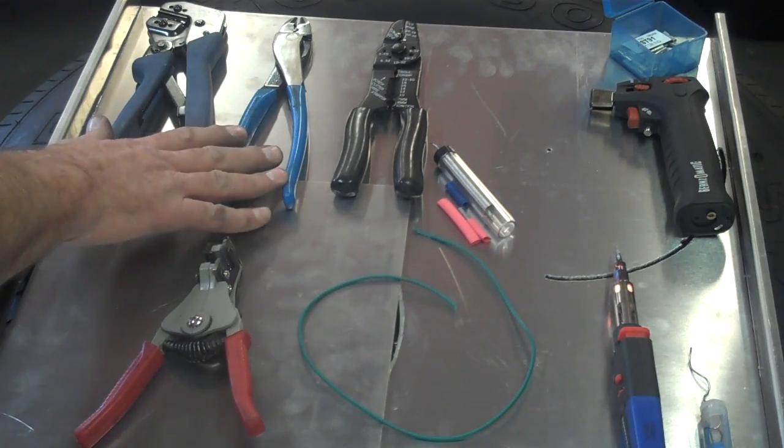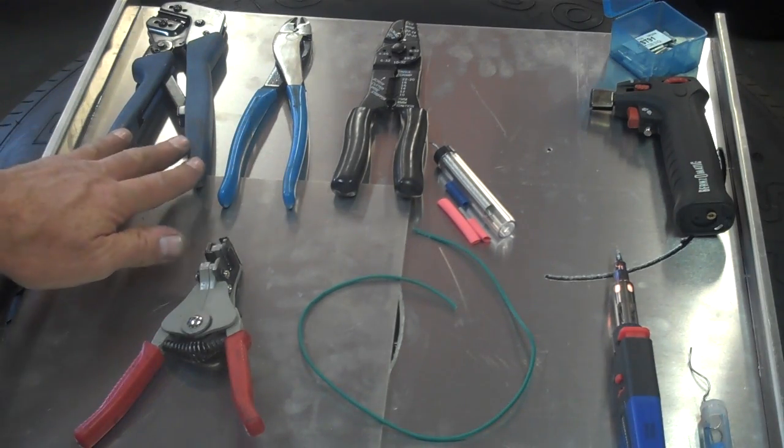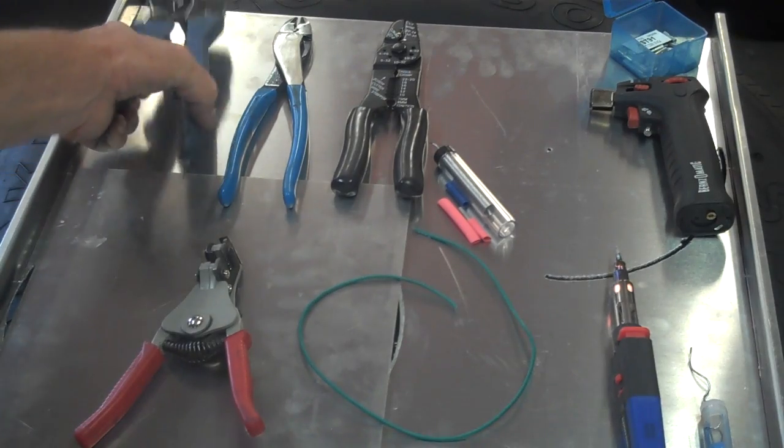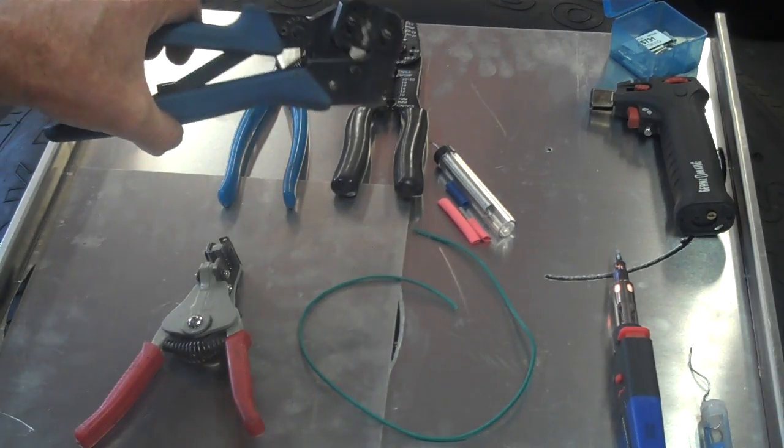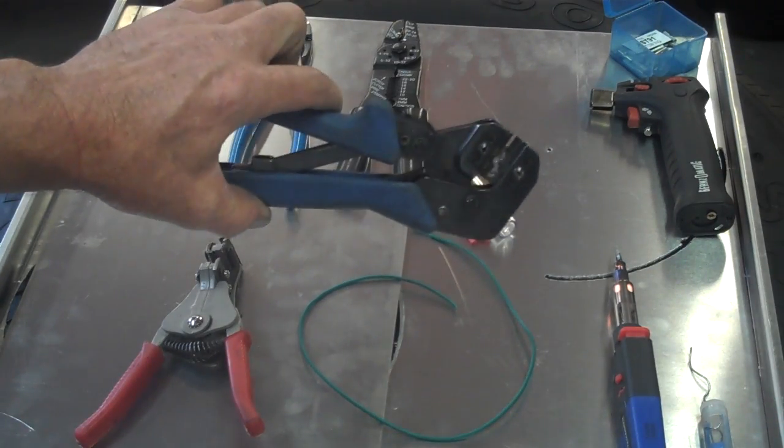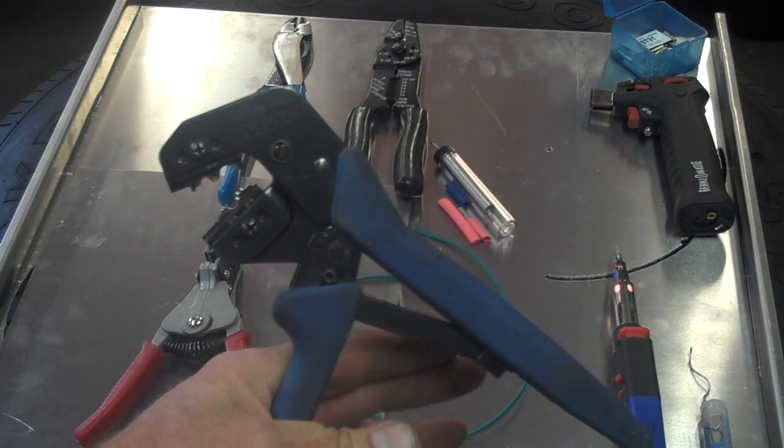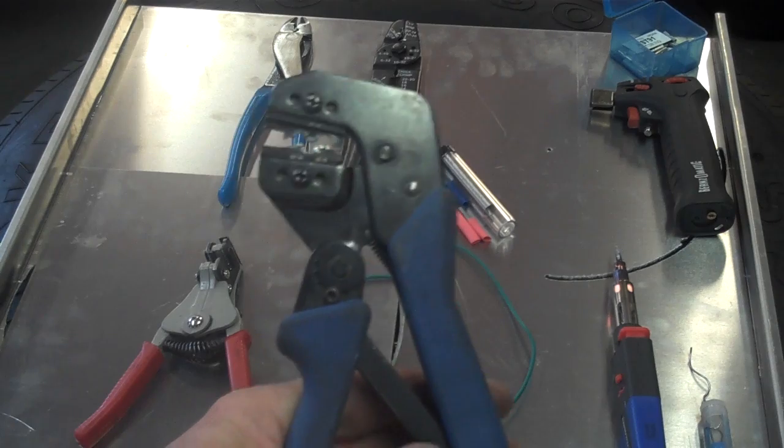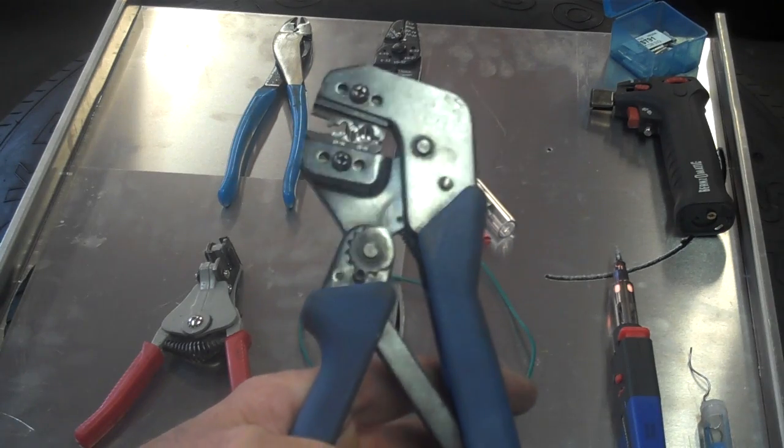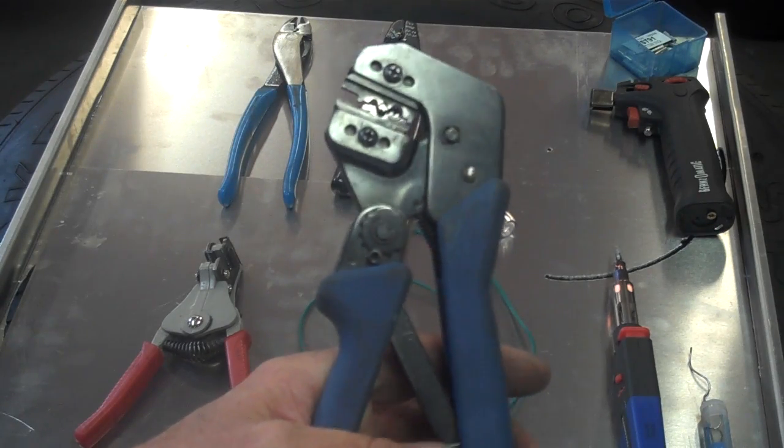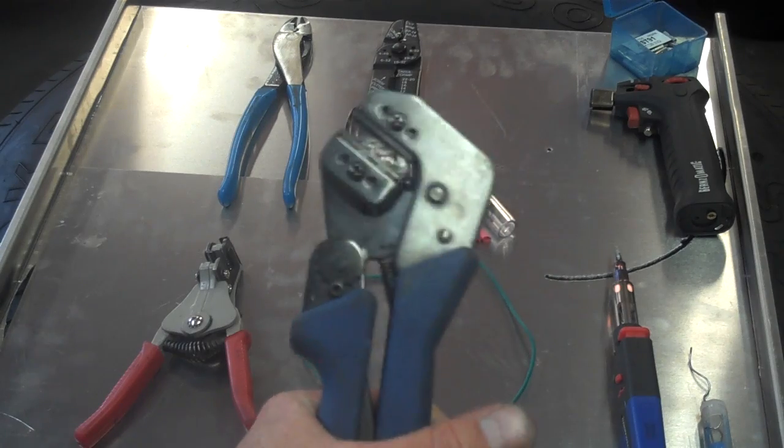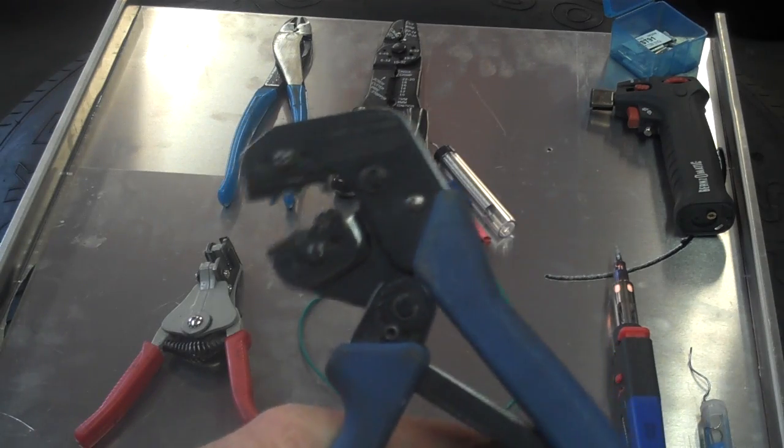Up here are some different types of crimpers. This is a lever-action type crimper that we would use for making a connection when we're dealing with non-insulated terminals. You don't want to use these any time you're working with an insulated terminal because these will just crush the insulation and keep the insulation from sealing against moisture.